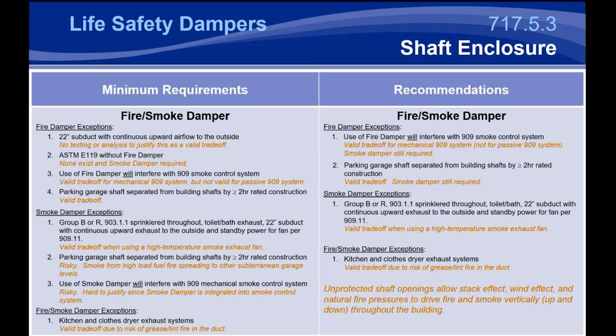Now, if you're dealing with anything that has a fuel source, so any duct that's for kitchen or clothes dryer exhaust systems, we definitely recommend removing the fire smoke damper for those applications. Any damper that's in that barrier is going to create a point of ignition, whether it's a grease buildup or lint buildup, that's going to create fire in the duct, and it's going to cause way more problems than the damper can protect against.